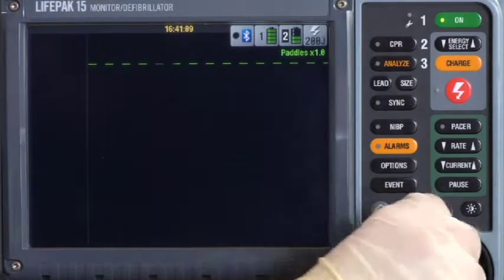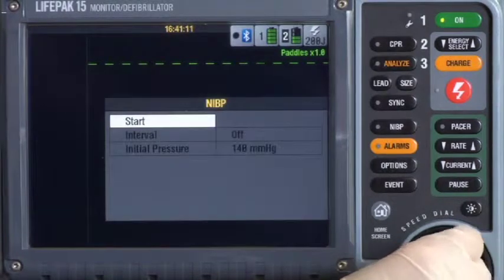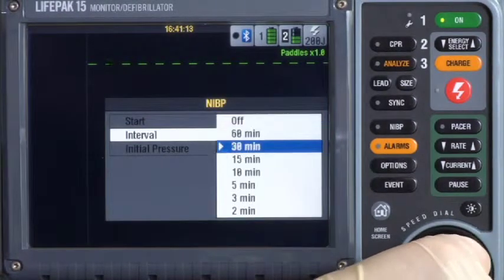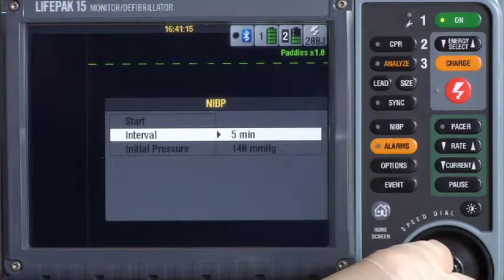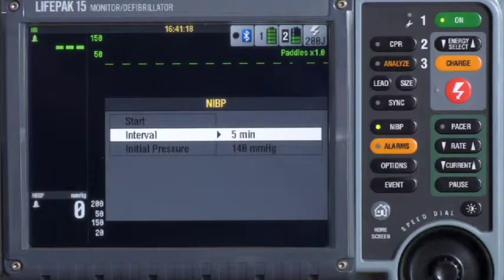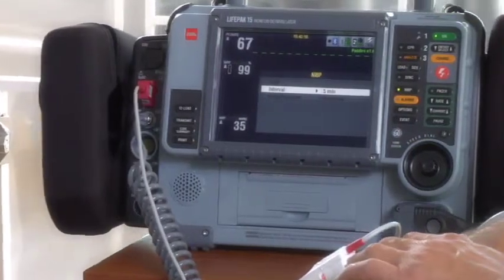Select the NIBP area. This time, select interval and choose how many minutes you want between measurements. We'll choose 5. Select Start or press NIBP, and the LIFEPAK 15 will take a pressure at 5-minute intervals.